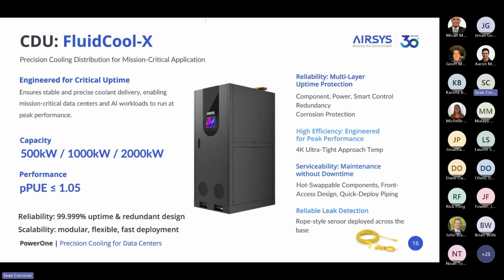Our Fluid Cool X, which is our precision cooling distribution unit, also comes in 500 kW up to 2 megawatts. We are actually in the midst of our product development of doing a 3 megawatt product set, because what we've heard from some customers is that bigger is better. It is 95% serviceable from the front and rear, and you can have the piping from top or bottom. And you can also daisy chain up to 8 of these CDUs on one controller, and you can put them side to side, thus giving you some savings in the footprint.